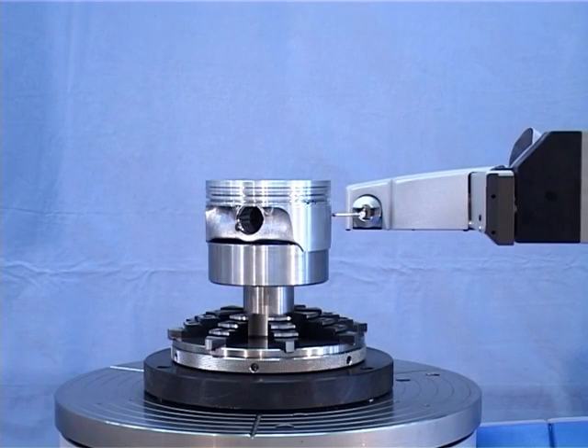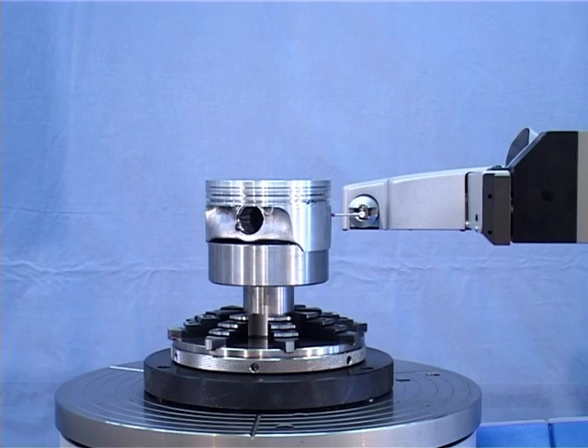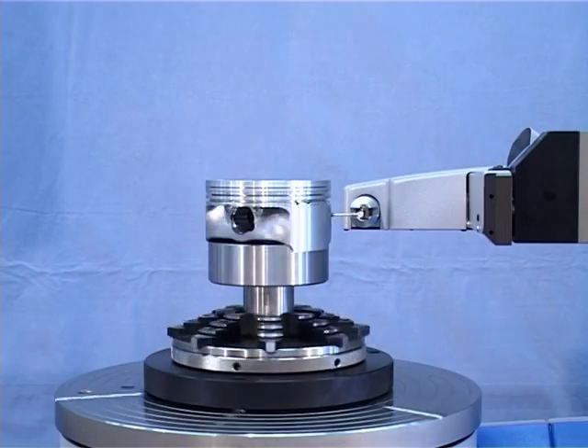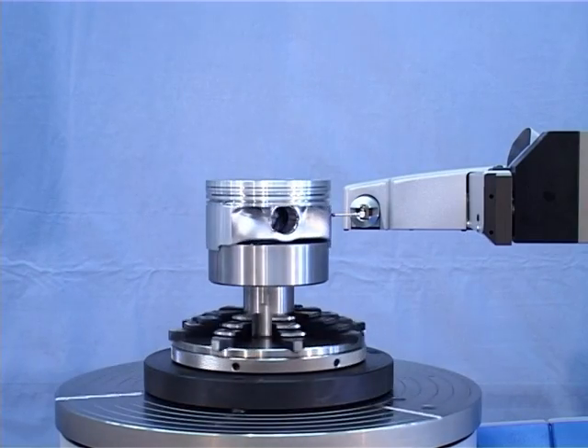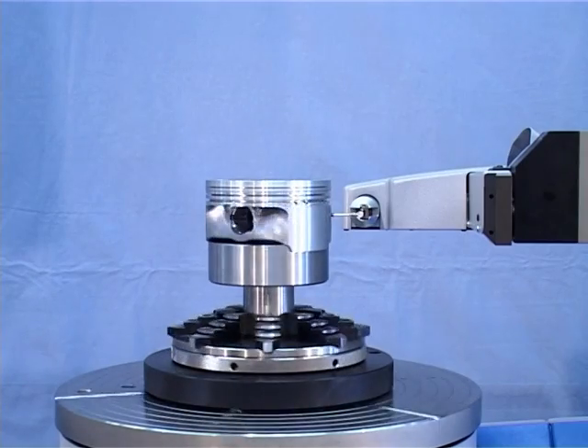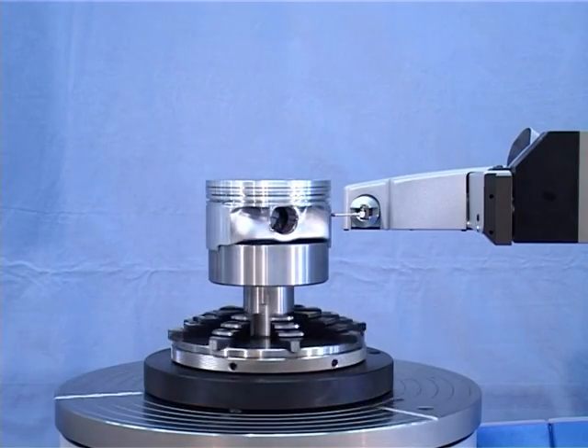An additional advantage is the large measuring stroke of the scanning system of ±1500 µm, which has an excellent linearity over the whole measuring range. This also enables measurements on workpiece geometries with considerable unroundness.